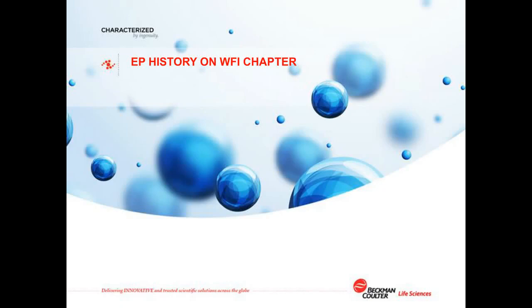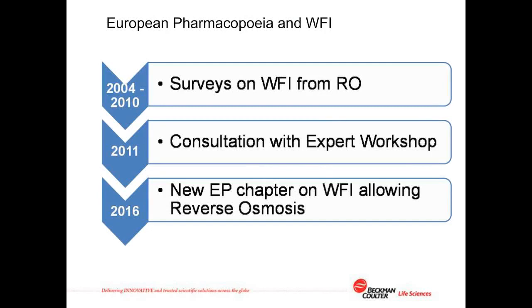So first of all, let's take a look at some of the history behind this recent change to the European Pharmacopoeia. Although much work has been done over the last decade to harmonise the pharmacopoeias across the world, the European Pharmacopoeia chapter on water for injection stood out because it specifically called for the use of a still for the manufacture of water for injection. Other pharmacopoeias merely listed the key quality parameters of water for injection, which are TOC, conductivity, microbial colony forming units, and endotoxin levels.